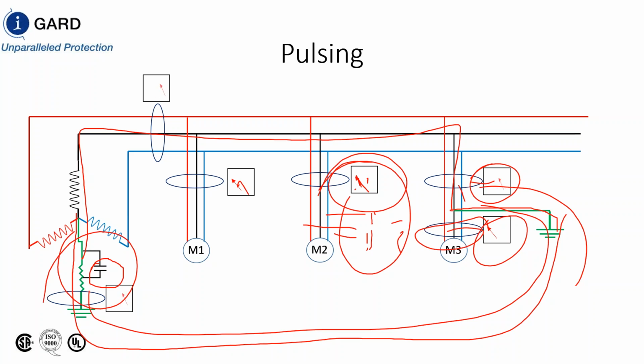Perfect, thank you. Next question, what are the advantages and or disadvantages of B-phase grounded systems? How difficult is it to switch from B-phase to HRG? There's one company that uses a lot of B-phase grounded systems, and sometimes it's easy to change, because if you have a true three-phase network, you're probably not going to have any fuses on B-phase. So you have to put in a fuse on B-phase. It's very, very easy to change a B-phase grounded system, if it's the traditional B-phase grounded system where you have all three phases there, to a high resistance grounded system by employing a zigzag transformer and a resistor. Everything else stays exactly the same.